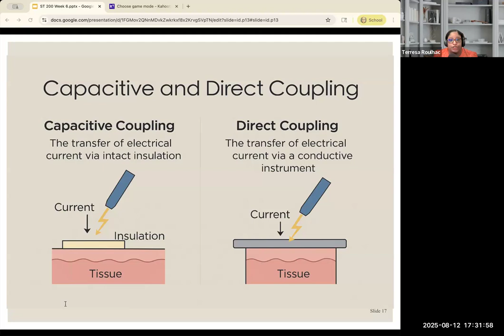So they both cause unintended injury, but the way that it happens is slightly different. Again, capacitive coupling leaks through the insulation. Direct coupling, the current flows directly from one conductive object to another. So one's going straight to it, the other one's spilling out and then getting it. Okay. But why is this important to us? Well, both can cause serious burns or injuries. So we're always going to inspect our insulation. We're always keeping our equipment maintained. And then we're going to monitor our ESU unit during our procedures.